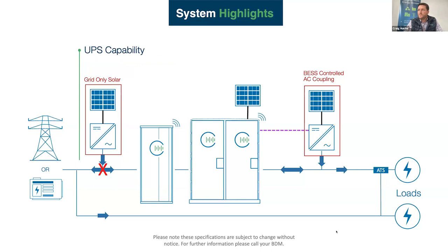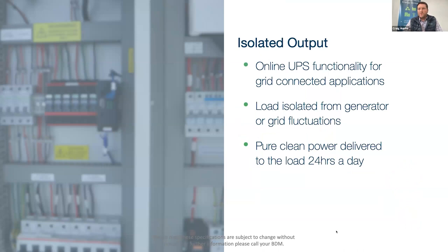When we talk about the inverter technology, where we get the UPS capability and also the isolated loads, one of the beautiful things is that your load is totally isolated from any generator or grid fluctuations. So you're getting pure, clean energy delivered to those loads on the output side of the product.